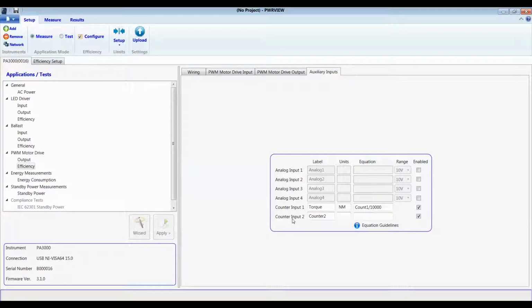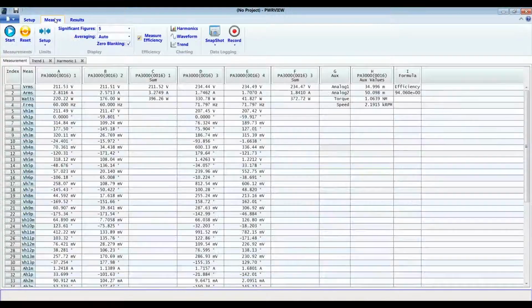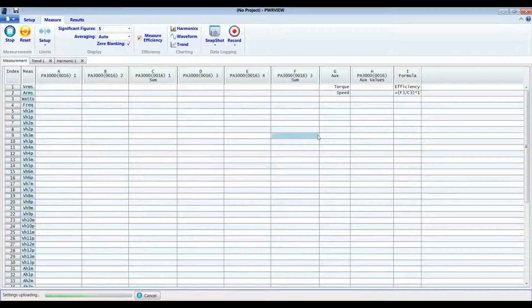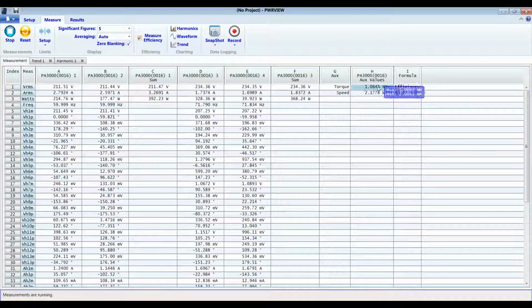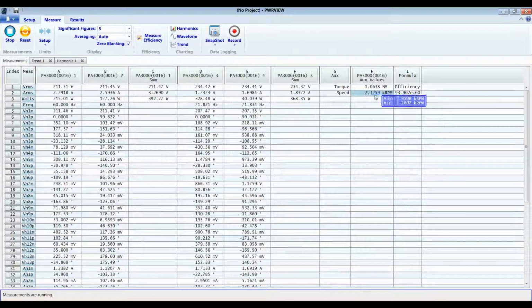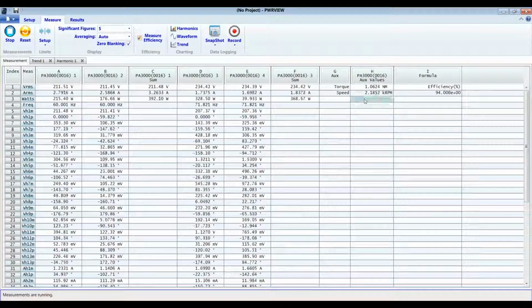Okay? For example, we can set up the second counter input, as you can see here, as a speed input. Okay? I'm going to enter the unit as RPM and enter the conversion ratio if you have any based on your sensor, right? Similarly, you can set up the torque, temperature or any other sensor inputs you might want to measure. All right, so let's go back to the measure grid, and there you have it. There, that's where it shows up, right? So it will show up as torque and speed, and it will have whatever conversions you had with the units on it. Okay? Obviously, I don't have a calibrated sensor connected to the aux terminals right now, but you can see how simple it is to configure such inputs.